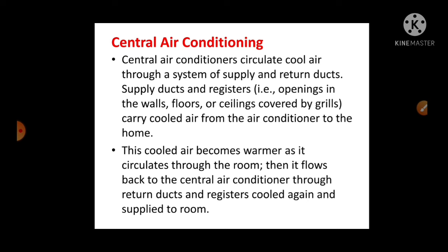to the room. In a central air conditioning system, in the vapor compression cycle, all the components, that is the evaporator, air handling unit, condensers and compressors, are located at one central place, either at the basement or top of the building, and cold air is produced. This cold air is supplied to the room through supply ducts and registers, grills in the room, and again through the grills this air is taken through the return to the central unit, cooled again and supplied to the room. This cycle goes on continuing.